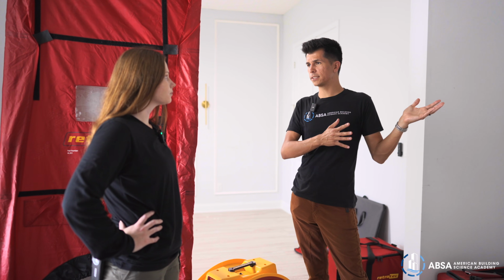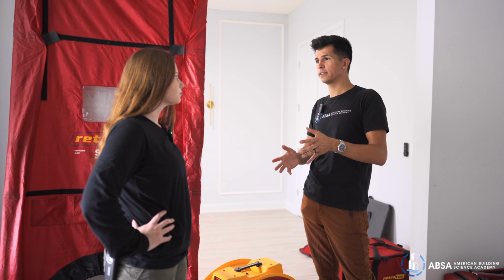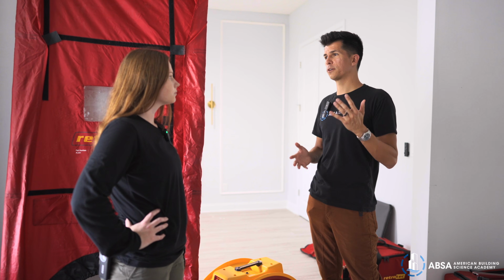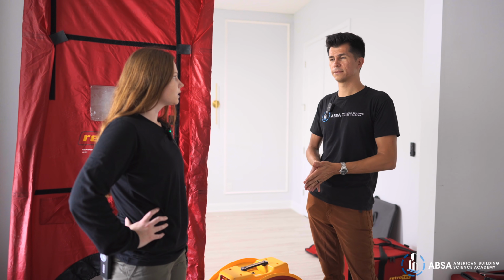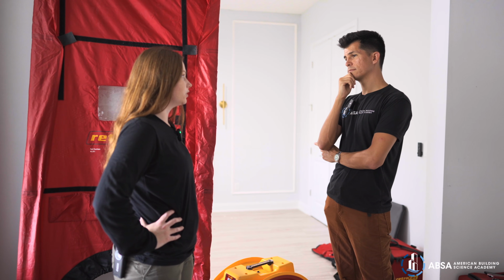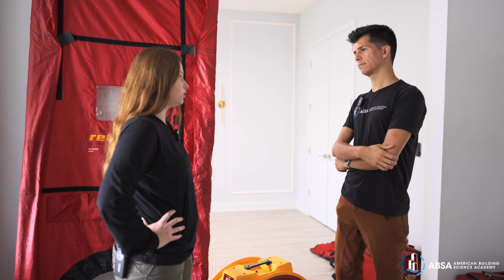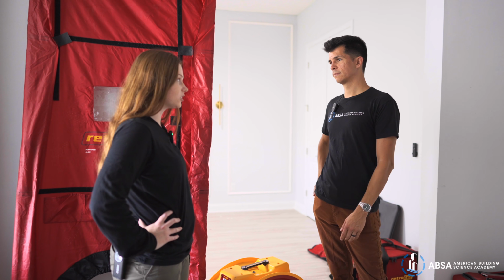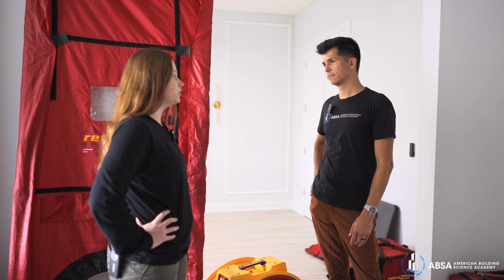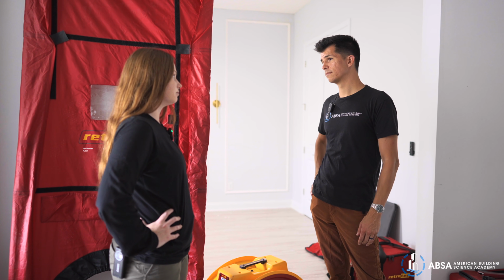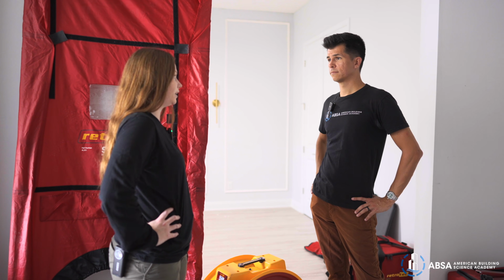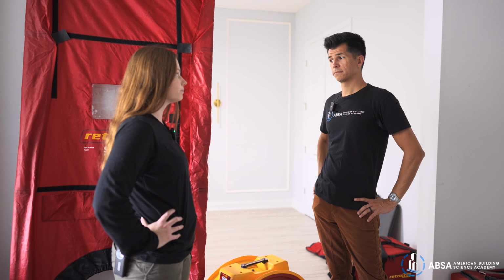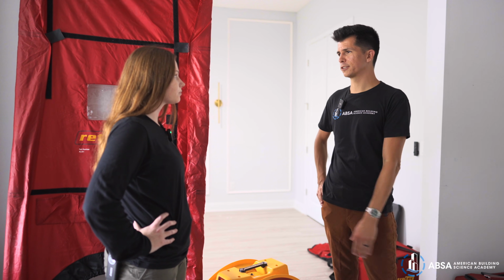But what about the HVAC? I know they installed an old unit into brand new ductwork. So how are we going to take a look at that? We're first going to do a duct leakage test. It's going to tell us how airtight the ducts are. We're also going to look at airflow and static pressure on the unit just to see if it's dehumidifying properly, how much restriction there is. And then we're also going to do a room-to-room pressure test, looking for supply, return, airflow imbalances. That's great. Awesome. Well, I'm excited. I'll let you get back to it.